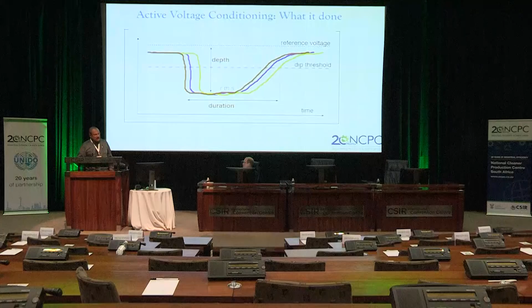If voltage drops there, it will remain there until the fault in the network is cleared by some breaker. Some overcurrent protection clears the fault. Now the voltage just recovers back to the value it was before the dip occurred. So for a period of time, a duration, we lose, in fact, some energy being served. That is what makes equipment stop, or your TV at home being reset or switching off.